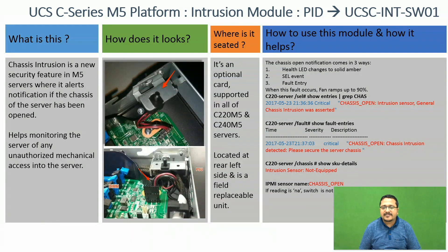The IPMI sensor name of this module is chassis_open. If the reading is 'na', that means the switch is not installed properly or is missing altogether.